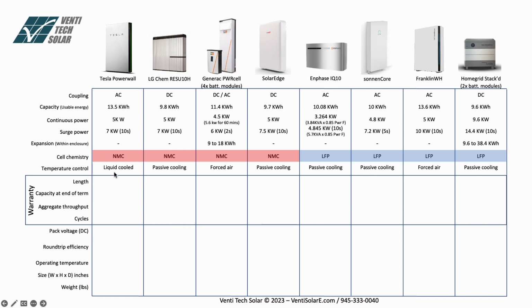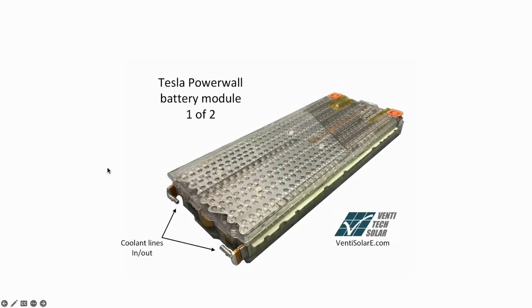The cell chemistry, we know about it, and the temperature control. This is a piece of information that very few people talk about, and it is important based on the cell chemistry. This value also plays a factor on the warranty. So liquid cool is what I will consider to be the top-notch cooling technology for any battery cell, especially the NMC. The NMC batteries need to be kept into a range so they don't go into thermal runaway. Tesla here is using liquid cool, a mixture of water and glycol. This is a battery module composed of many cells. The cells are these little circles that extend from top to bottom of the module. And these tubes are a ribbon of micro pipes that go all along the whole battery module, touching every cell, and then come out on this end.